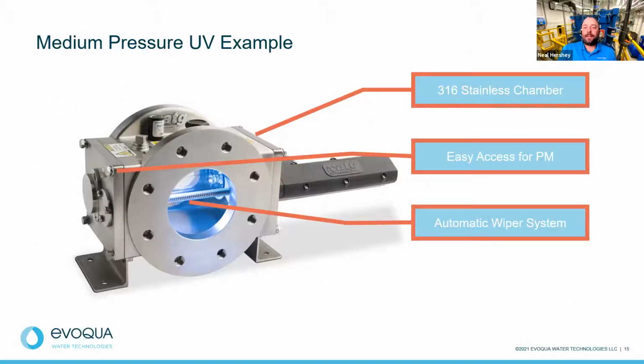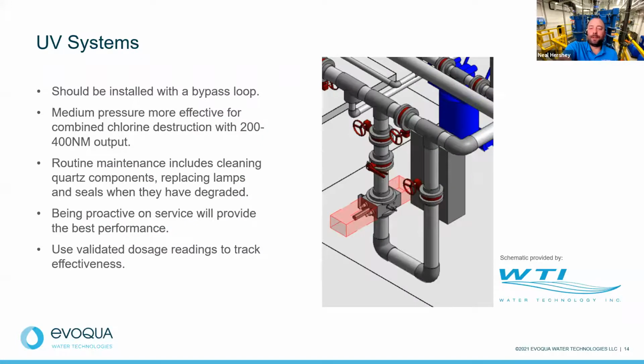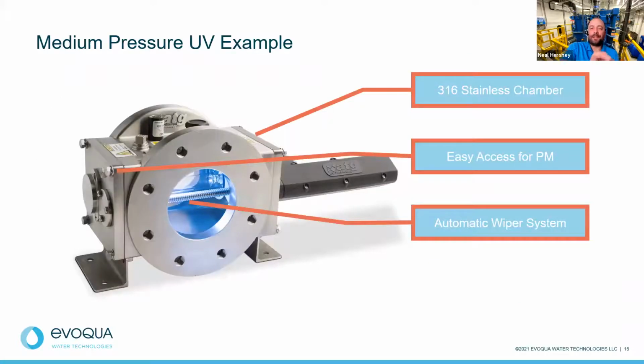So pointing this out, just a basic overview here. In this loop you've got the UV chamber, and this is basically what it looks like outside of a schematic. You generally have a chamber with the lamps and sleeves inside, and the basic preventative maintenance is to remove the lamps, remove the quartz, clean everything, replace the lamps depending on their age and output, and put everything back together. Included this for those who maybe haven't seen the inside of a UV system at this point. Pretty cool, pretty basic, but it does require routine preventative maintenance to work at peak performance.